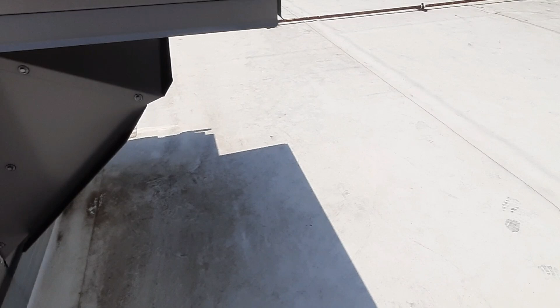So round two. I noticed when I went back down to check on that zone system, not used to looking at those T6s, but 205 also was not cool, and it was set on 74, I think. There was 70 something in there. So first thing I'm gonna do is get the disconnect open and verify I got power. This guy's itching to leave. He's got stuff to do apparently, so we'll verify I got power, and then we can go through this guy, see what's wrong with it.